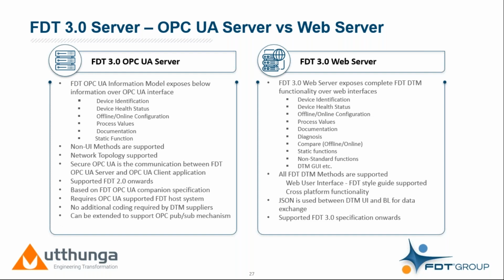The FDT OPC UA information model maps FDT interfaces to the OPC UA address space. With this model, we can expose device identification information and the entire network topology. For example, if the FDT server is connected to a Profinet gateway, which is connected to a HART device, it's possible to see this entire network topology as part of the FDT OPC UA information model.